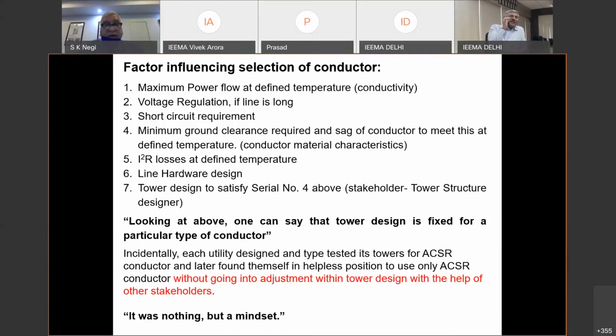Now, going to the little technical background, how these conductors are selected. One is clearly the maximum power flow at a defined temperature. The voltage regulation is also kept in mind when it is used in a long line. Short circuit requirements are definitely important for selecting the size of the conductor for a particular voltage level. Then minimum ground clearance required and sag of the conductor at a defined temperature. This is a very, very important factor which determines the tower cross arm height, the bottom cross arm height. I square R losses, definitely this is one of the important factors, and cost benefit analysis is done based on this only.